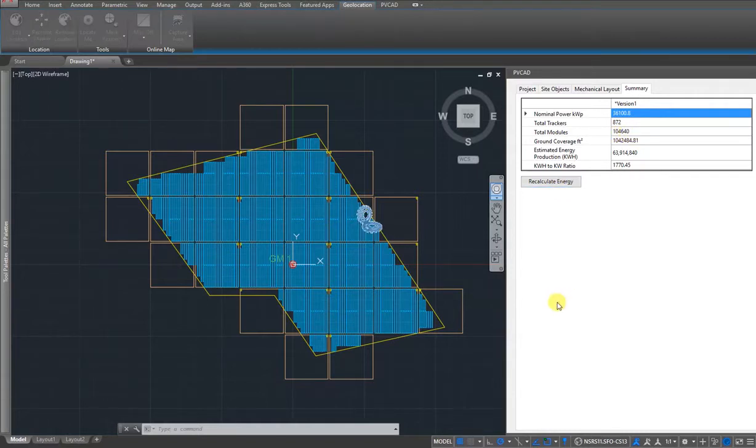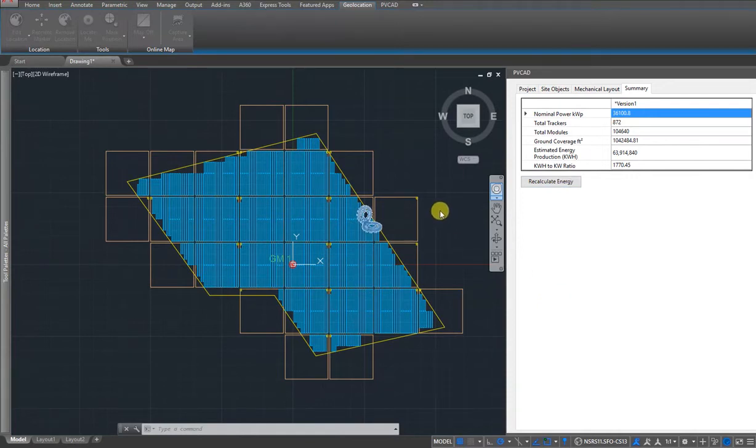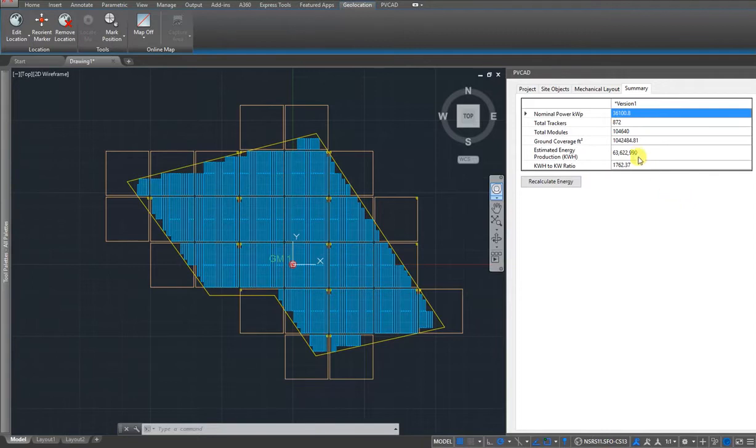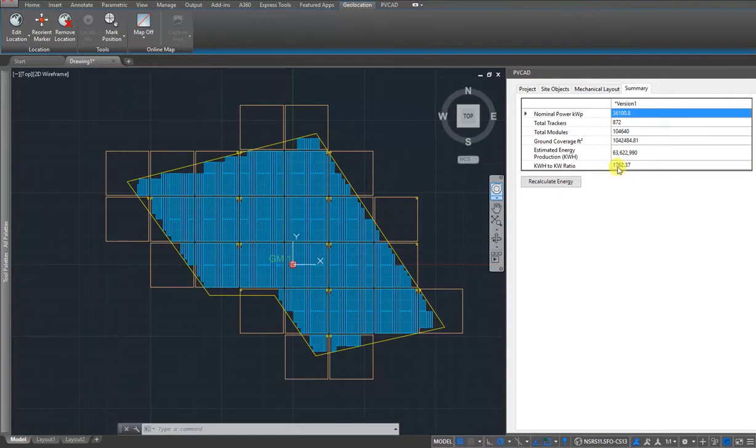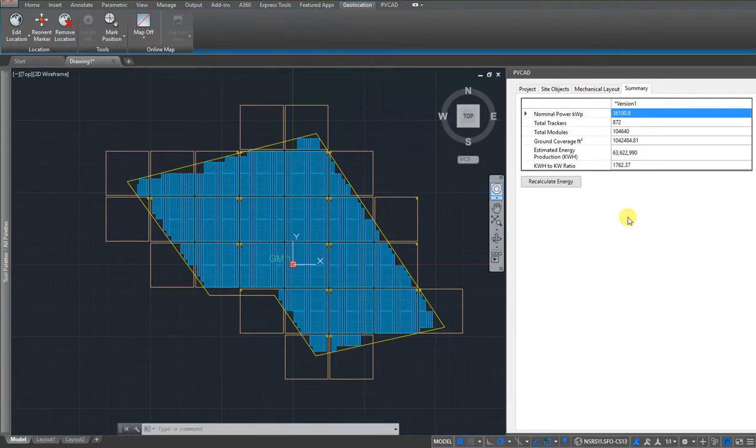We can also recalculate energy and see how much the system actually produces in one year. You can see the kilowatt hour to kilowatt ratio is 1,762 kilowatt hours per kilowatt, which is roughly what we would expect for a single axis backtracking system.